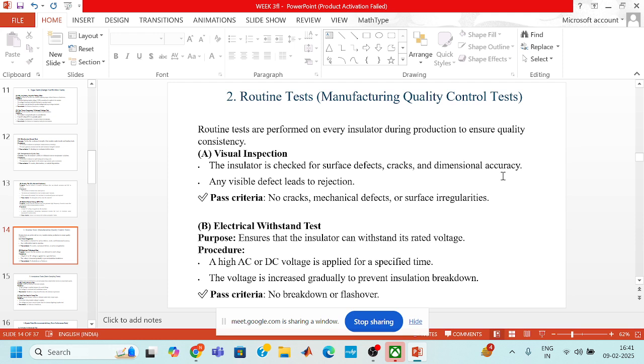Now, part B is the electrical withstand test. The main purpose is to ensure that the insulators can withstand their rated voltage. First we have to give a high AC or DC voltage for a specified time, and the voltage is increased gradually to prevent insulation breakdown.